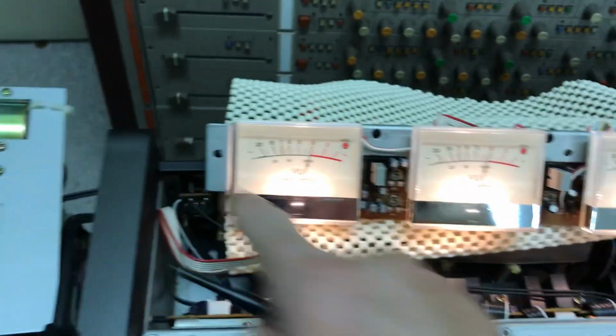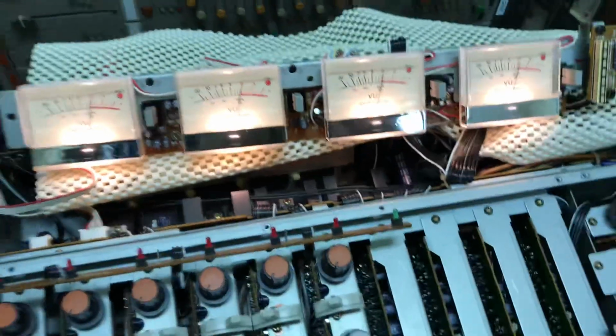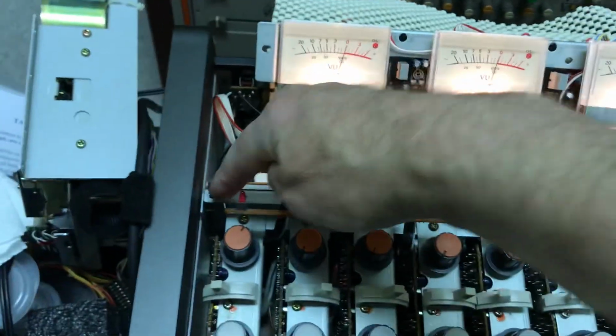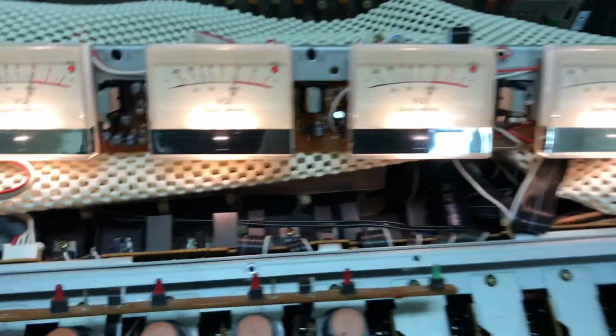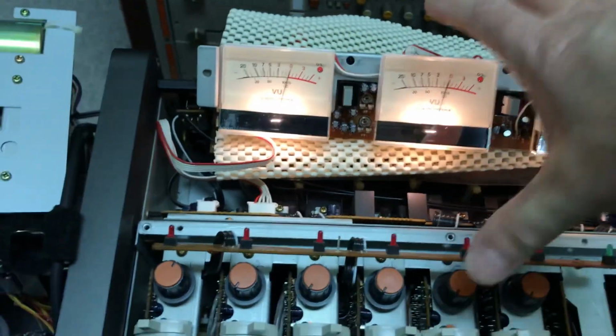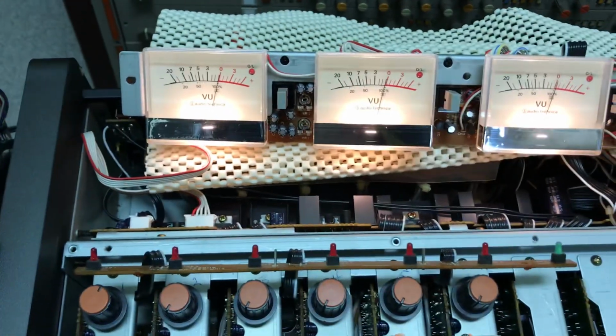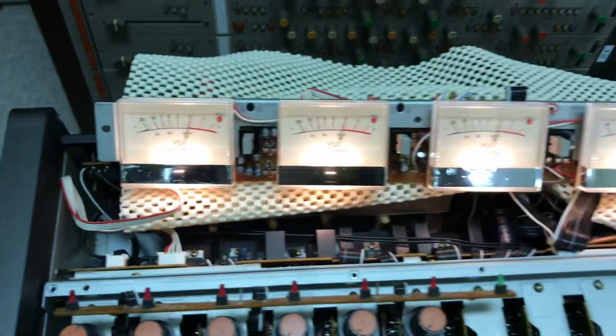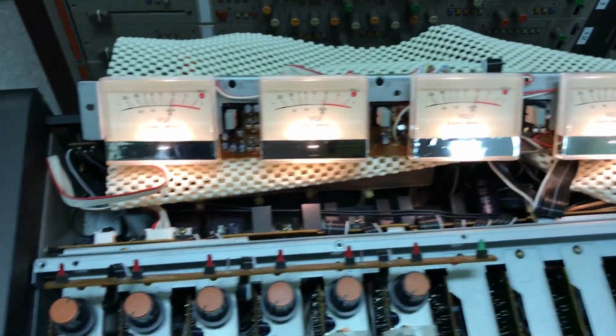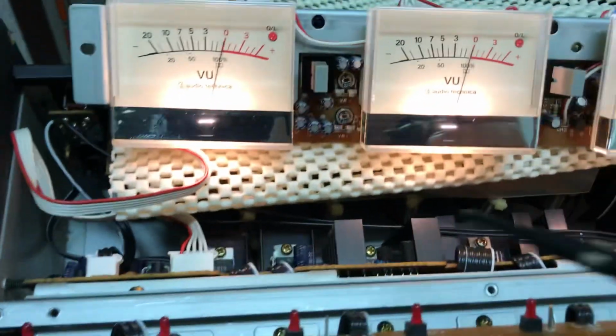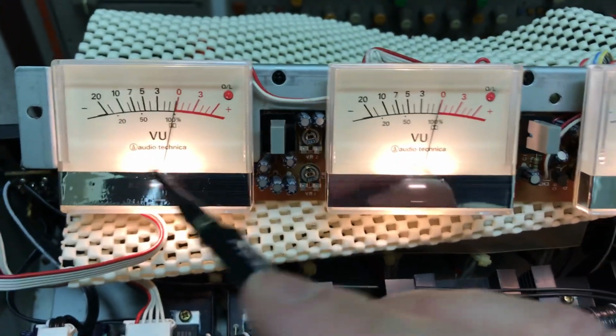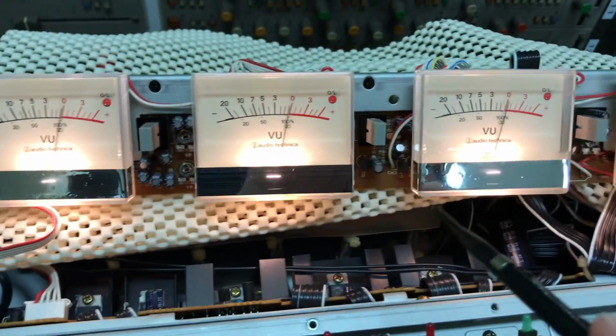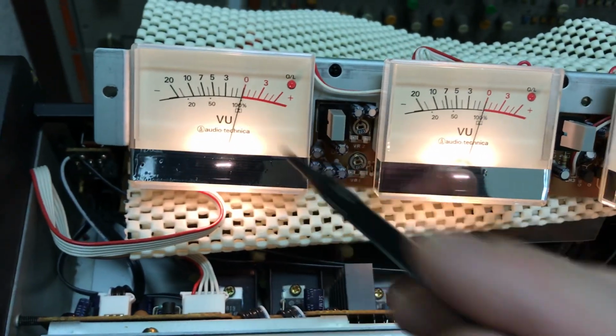But they're held in by 3 screws to the back of the meter bridge housing. There's 3 screws up here and 4 screws in the back. Remove those 7 screws, the whole thing lifts up, and then there's 3 screws that hold this whole assembly to the meter bridge housing. And once you have it exposed, then you can get to the trimmers on the meter amplifier PCB that trim each meter.